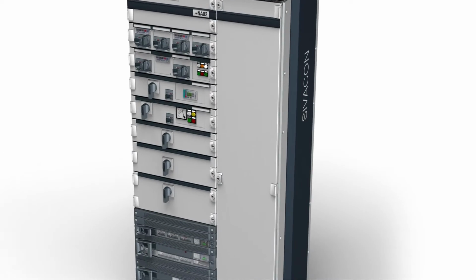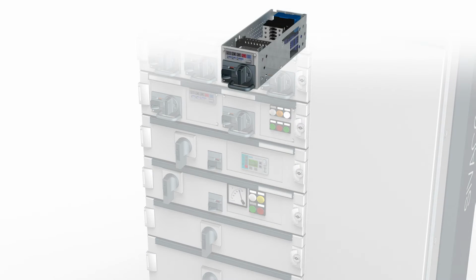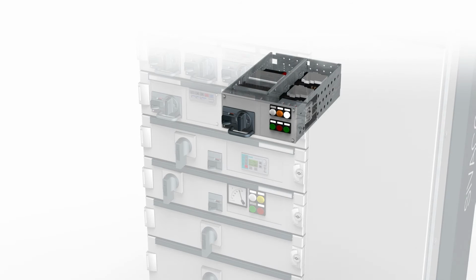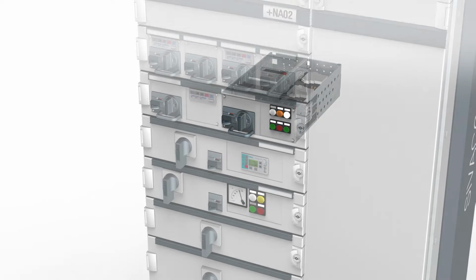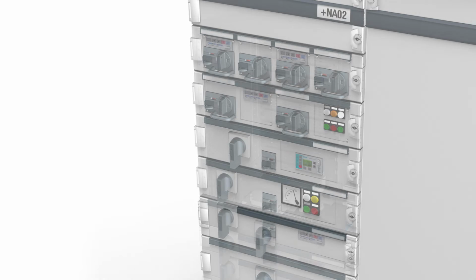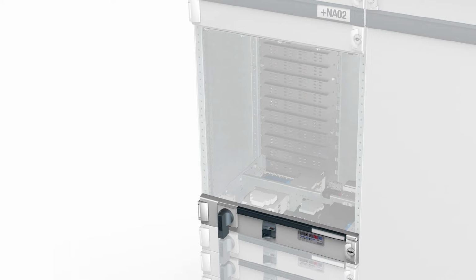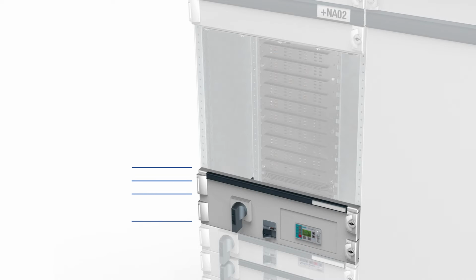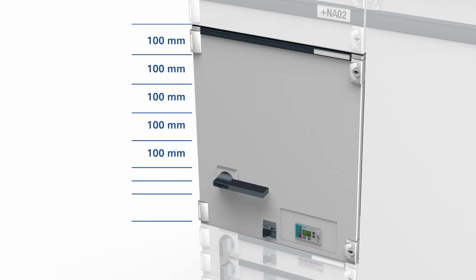Withdrawable unit widths of 150 mm, 300 mm, and 600 mm facilitate flexible and modular assembly according to customer requirements. Between 100 and 200 mm, the rack heights have a 50 mm grid size. Between 200 and 700 mm, a 100 mm grid size.